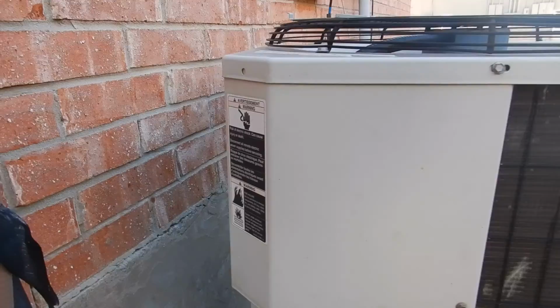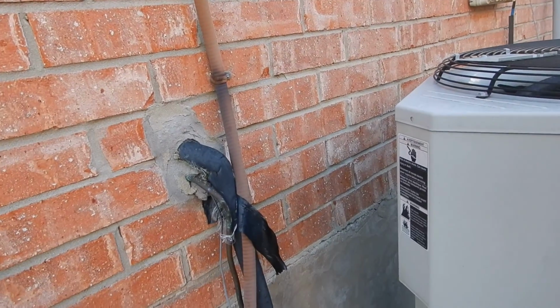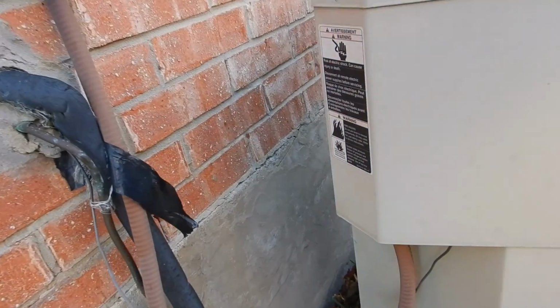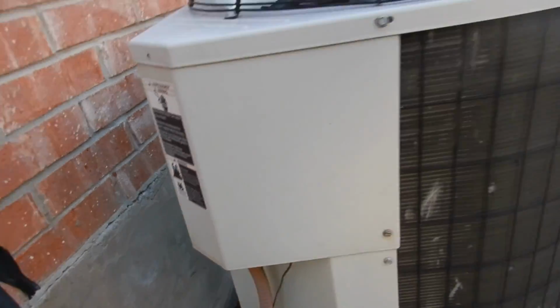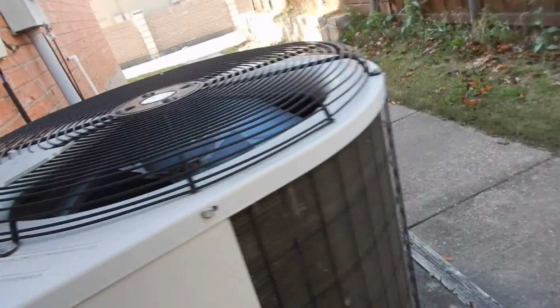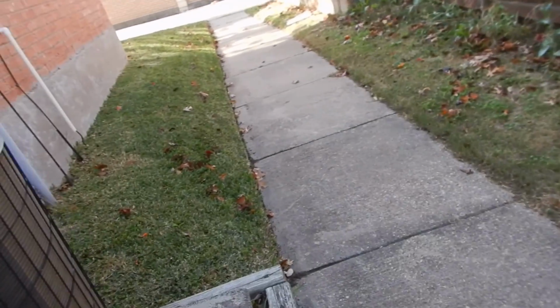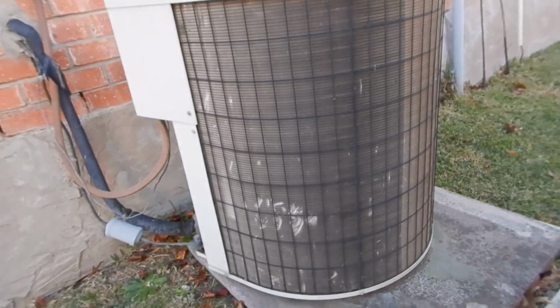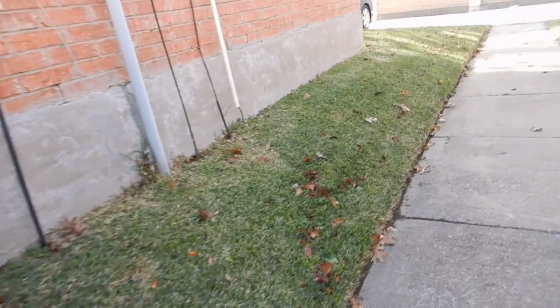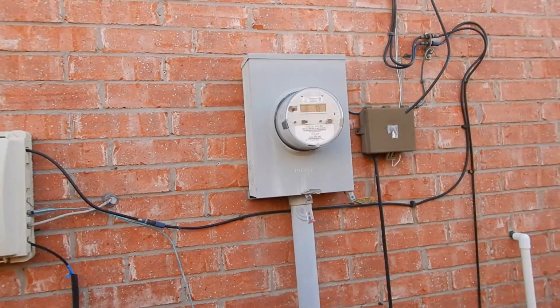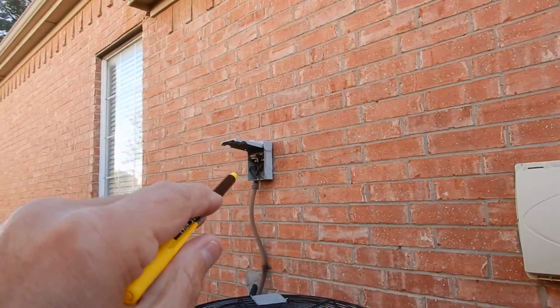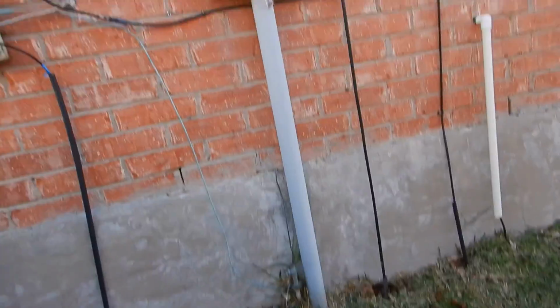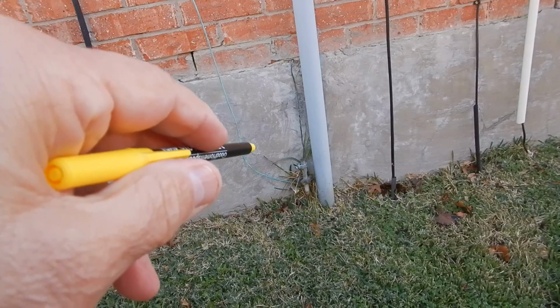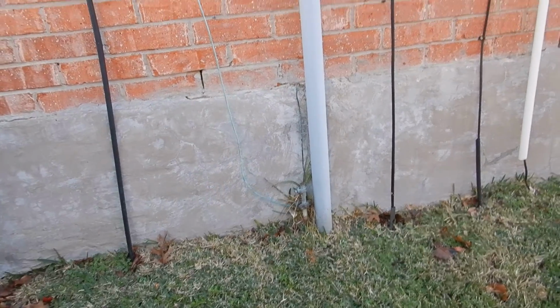We learned that we do not have an electric service receptacle outlet out here. We learned that we've got the wrong kind of foam. We don't have anti-theft Schrader valves. We learned that some of our damage is impact damage on the coils, but we also learned that we've got dirty coils because the unit is too close. We learned that this unit is 19 years old and that it's R22. We also learned that our electric service panel, our electric meter box, should be sealed on 3 sides like the disconnect should be.